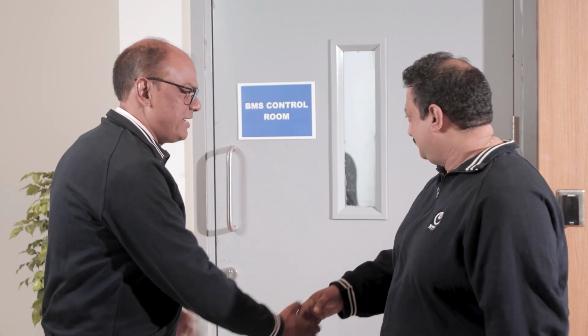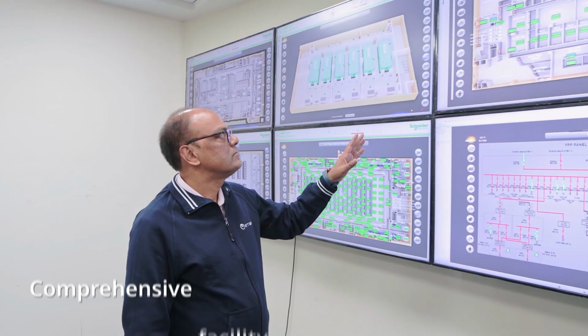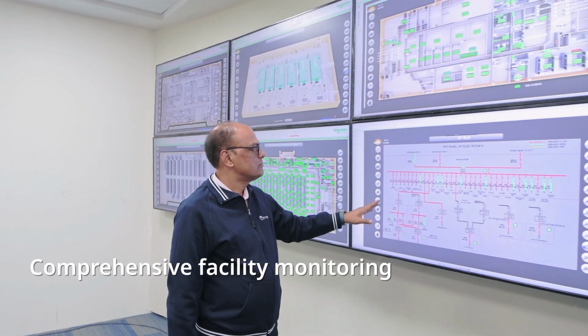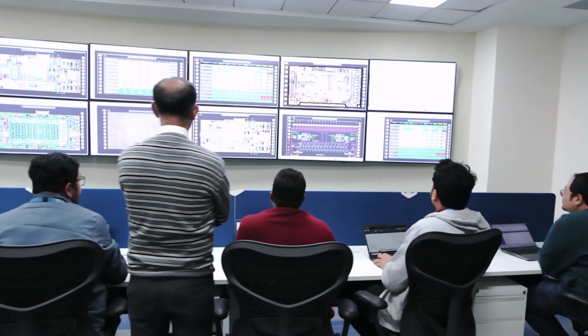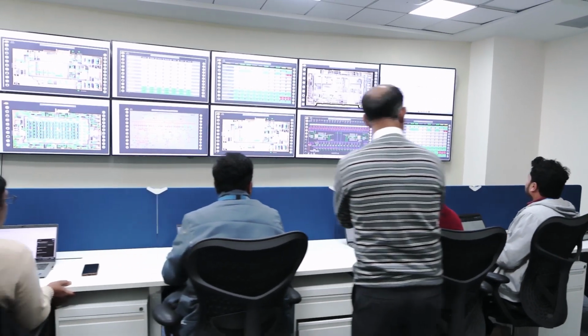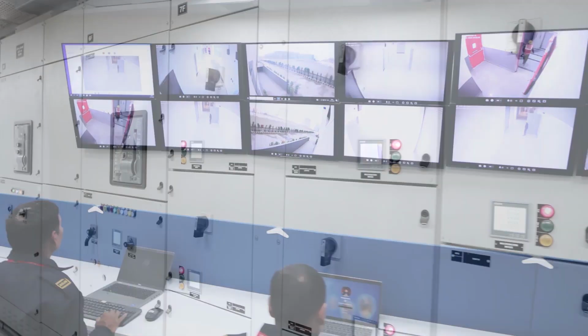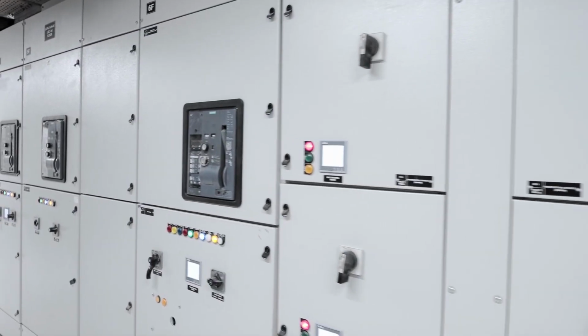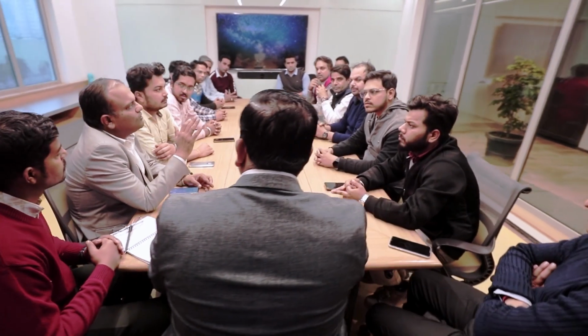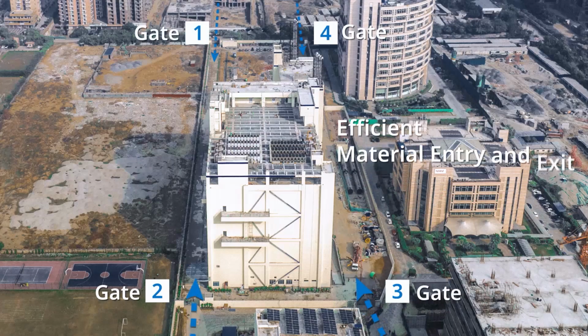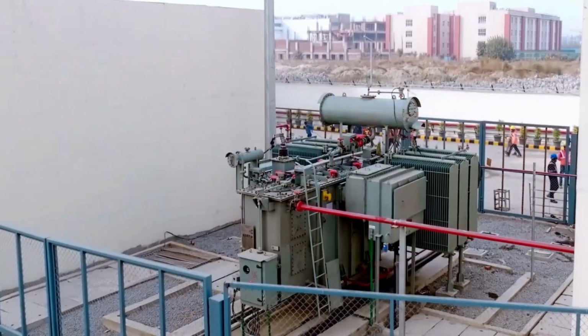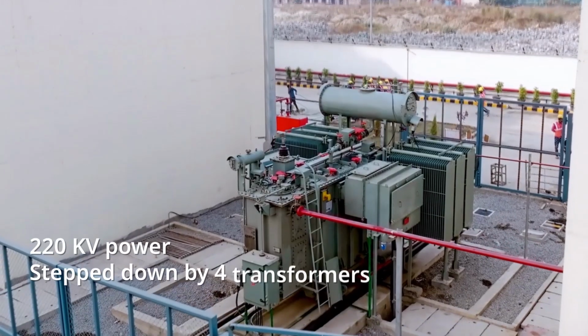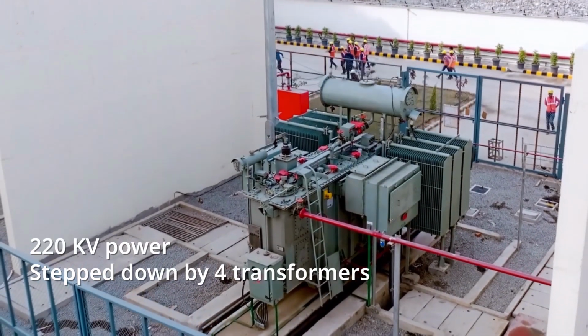The ground floor houses key operational areas such as the BMS room for monitoring electrical components, mechanical systems, and server hall parameters. The CCTV room for surveillance and the electrical room for power distribution. The customer seating area provides a comfortable space for client teams to work, while the material entry-exit area facilitates efficient equipment handling. The data center receives power at 220 kV and steps it down to 11 kV using four power transformers in N+1 redundancy mode.